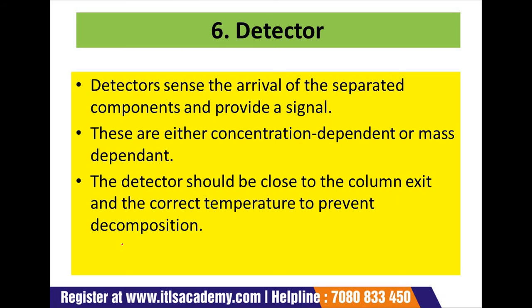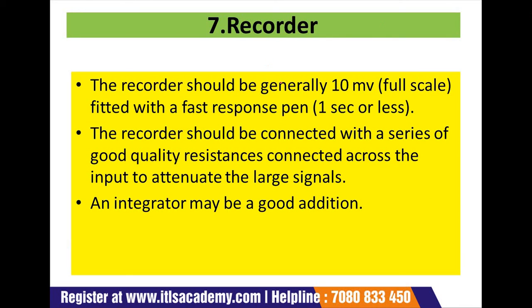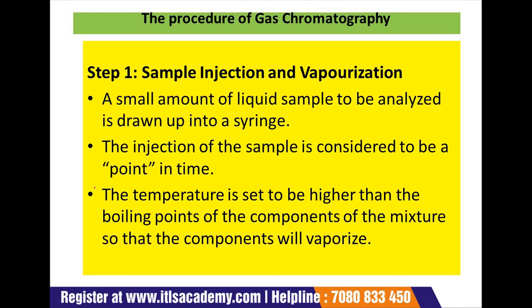The detector senses the arrival of separated components and provides a signal. These are either concentration-dependent or mass-dependent. The detector should be close to the column exit and at the correct temperature to prevent condensation. The recorder should generally be 10 mV full scale, fitted with a fast response pen (1 sec or less). The recorder should be connected with a series of good-quality resistances across the input to attenuate large signals. An integrator may be a good addition.